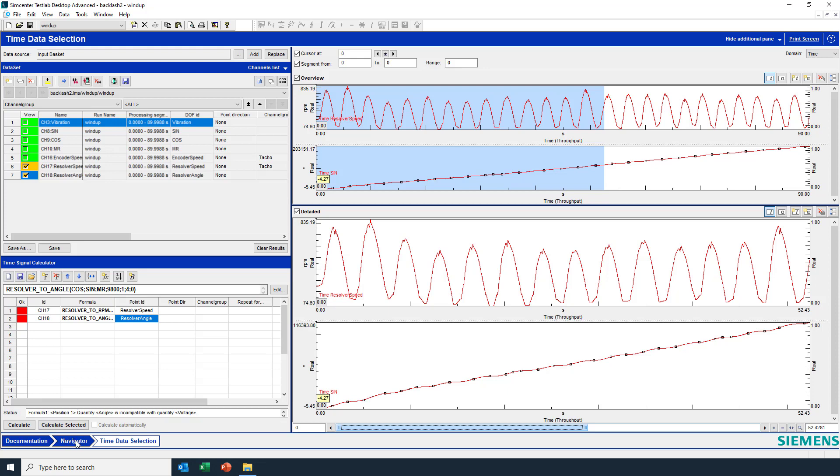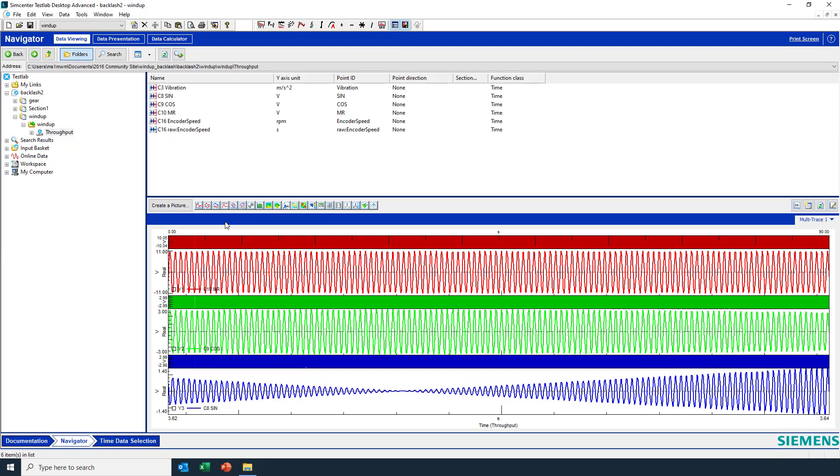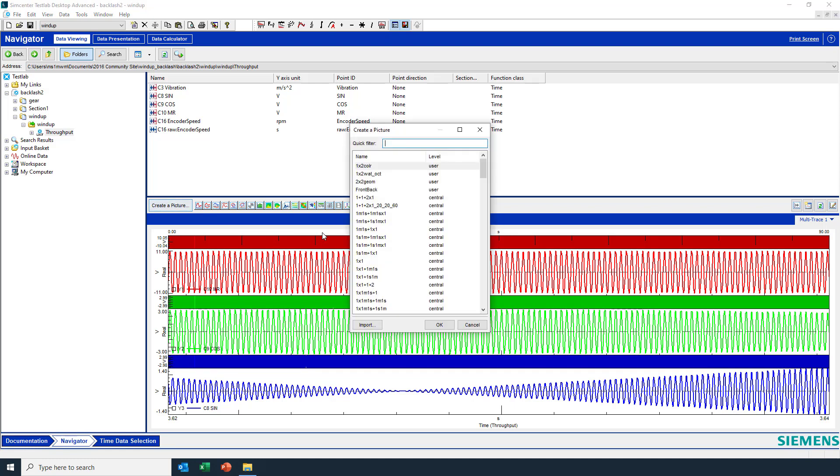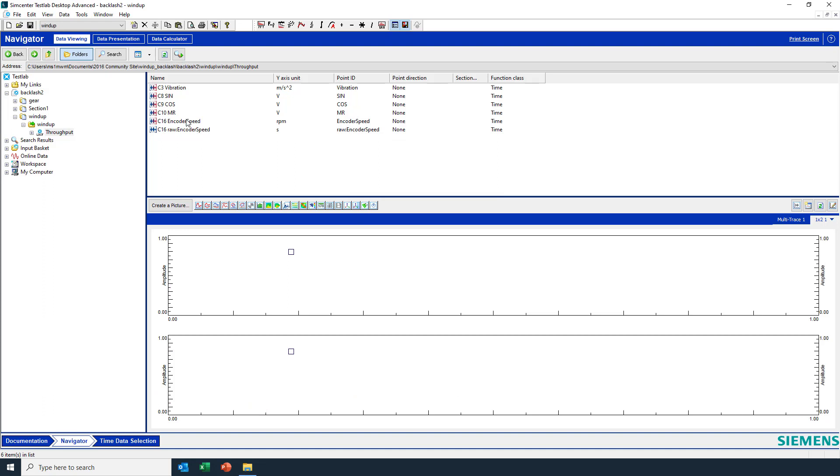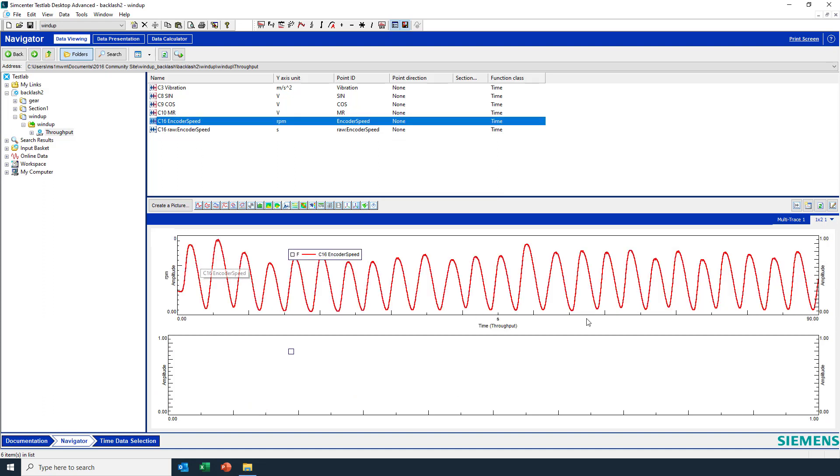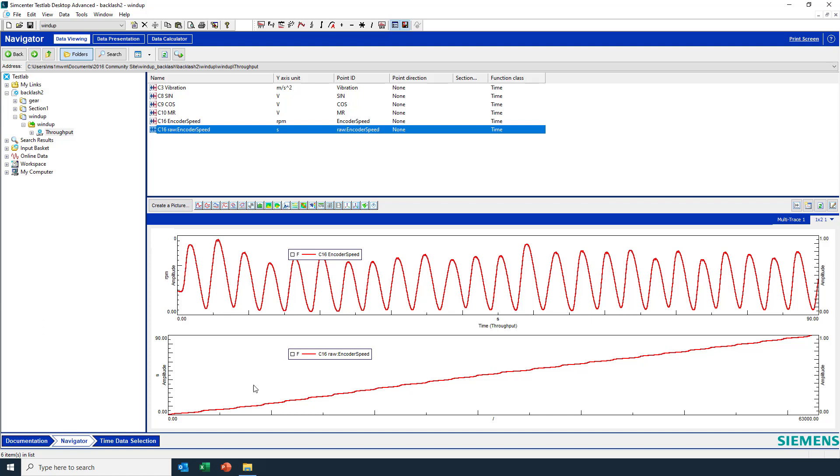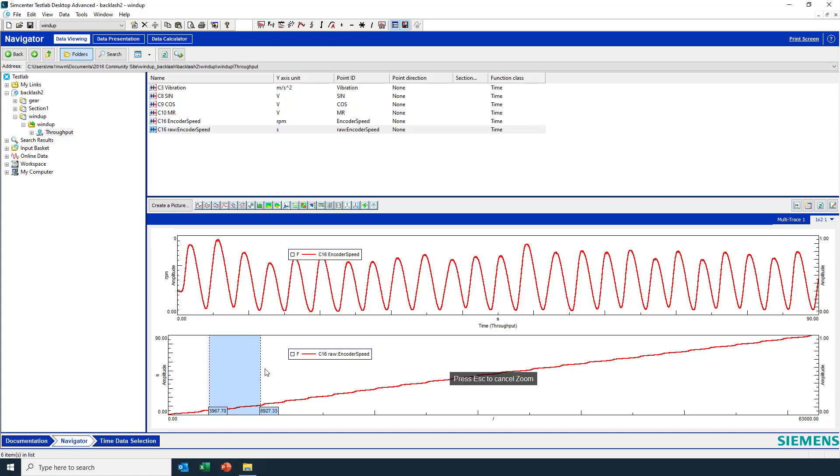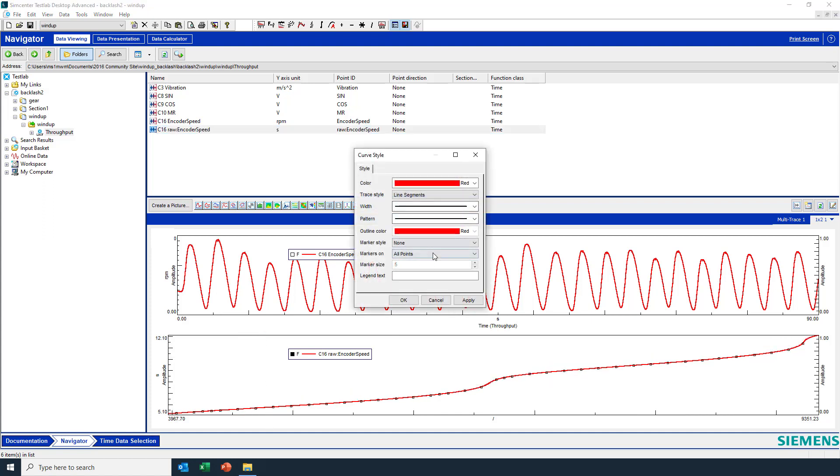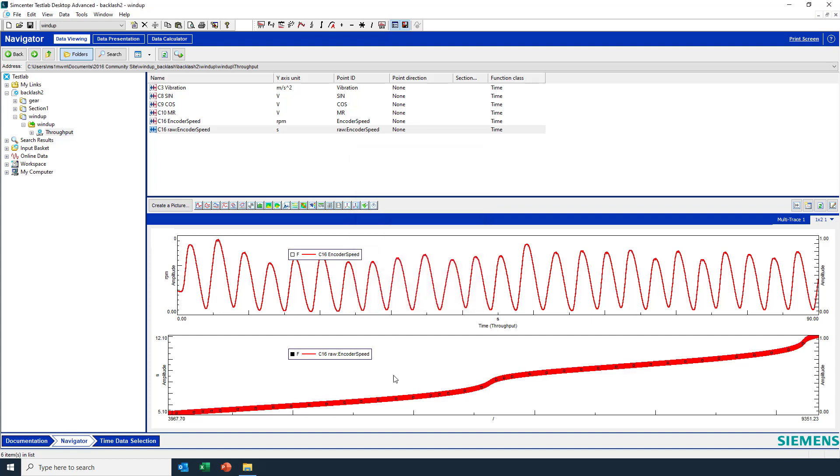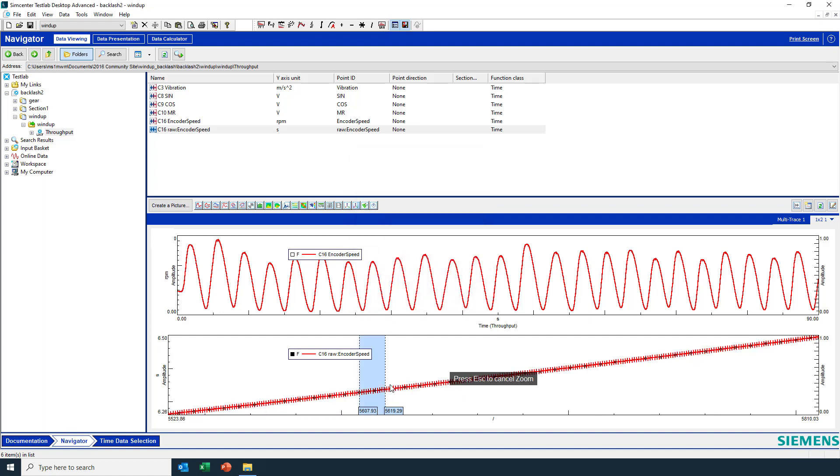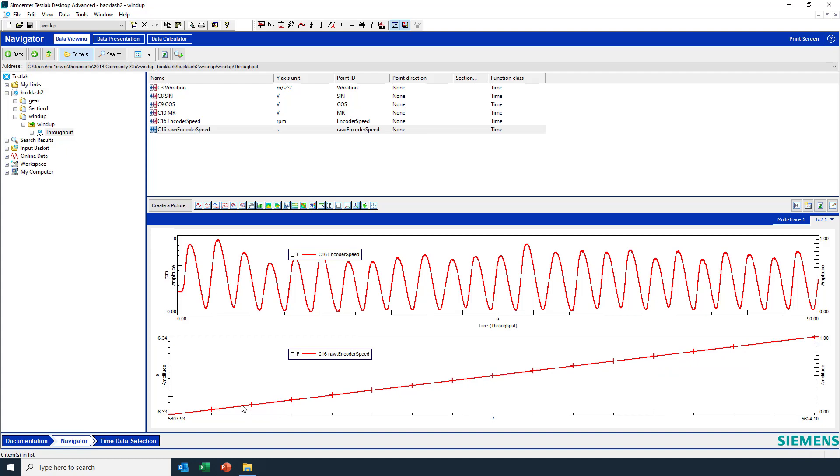Now I want to analyze the encoder. For the encoder I have two pieces of information. I have the speed versus time, so this is the rpm. And I also have a special trace called a raw trace, which is the moments in time or time stamps of the crossing. So this is the number of crossings on the encoder. You can see there was 833,000 crossings, and these are the times that they occurred at. If I zoom in a bit and change this to marker style cross, you can see if we zoom in enough exactly where those crossings occurred.